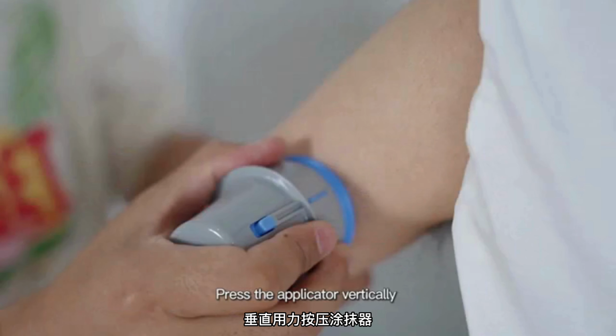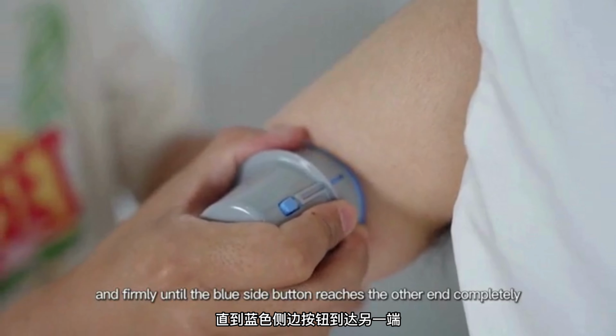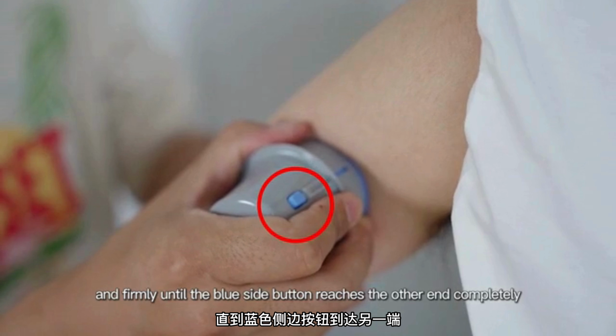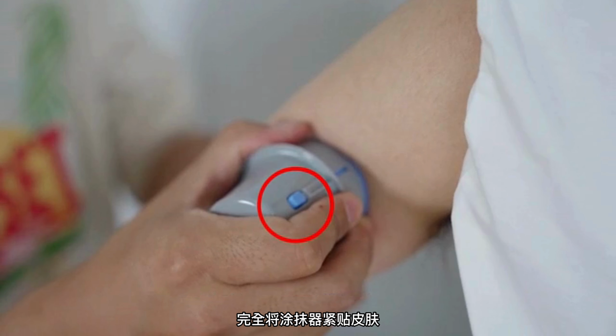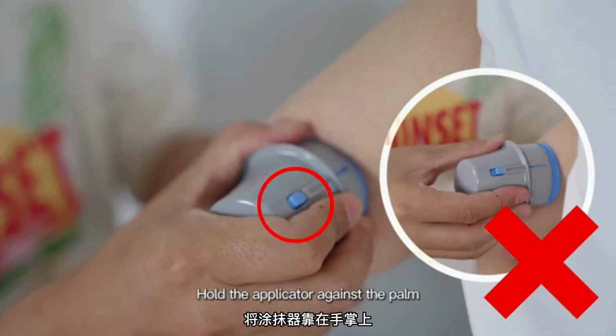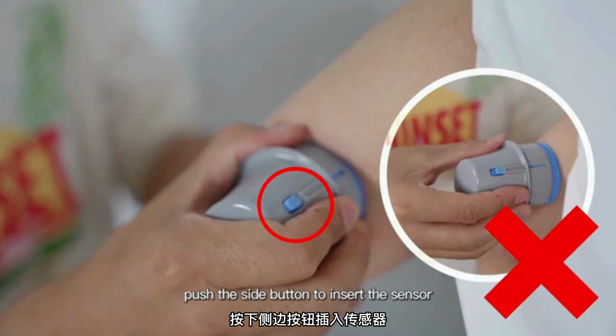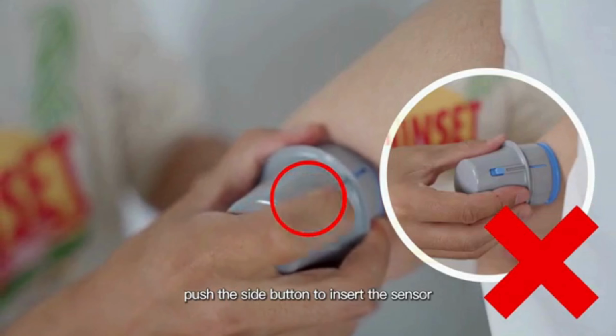Press the applicator vertically and firmly until the blue side button reaches the other end completely. Hold the applicator firmly against the skin. Hold the applicator against the palm. While holding down the applicator, push the side button to insert the sensor.